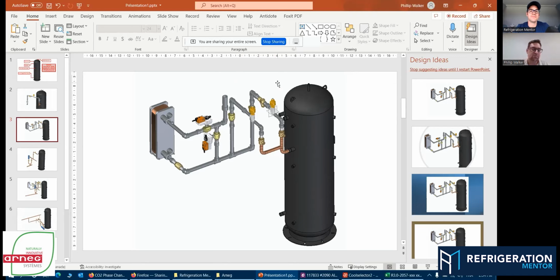With, I should rephrase that, with long lead times in the industries, it's been some of the technicians' worst nightmares where they have critical failures, and they're trying to source parts, trying to maintain the system going. When you have a supermarket, you lose this valve, it's a critical failure. Common process was to put a ball valve with a bypass. Well, we had technicians in our testing. We have a laboratory, just for anyone listening on, where we test racks, controls, and cases. And common industry practice was you put a bypass with some ball valves. And if this valve failed, you crack open the ball valve, so your wrench and yourself is basically mimicking this valve. A lot of the times what happened when we were doing so, if we weren't careful, we're losing gas. We're opening up the relief line.